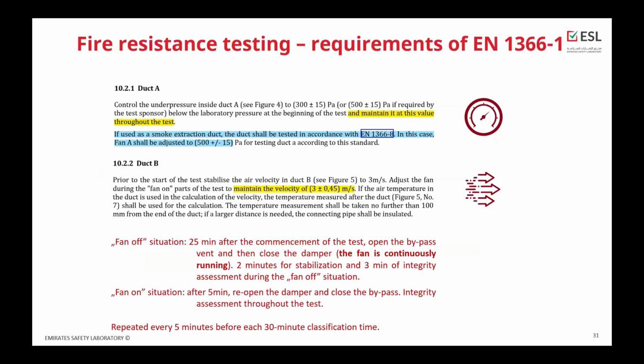The requirements for duct A and duct B are quite similar, the difference being that we are maintaining pressure in duct A and velocity in duct B. For duct A, there is also one more requirement: if this duct is intended to be used as a smoke extraction duct during the test in accordance with Part 8, the pressure must be increased to 500. The same scenario for fan off and fan on situation, but there is a different repeating time, only 5 minutes before each 30 minutes of classification.